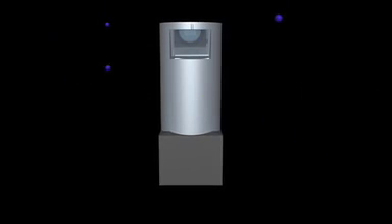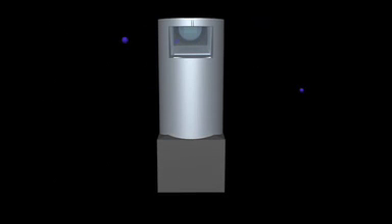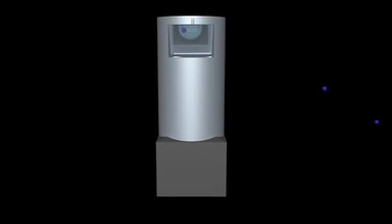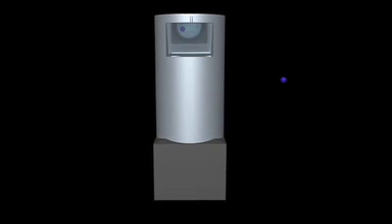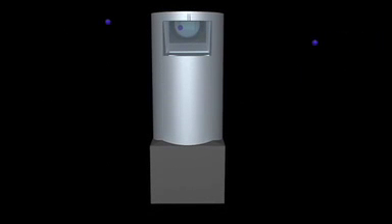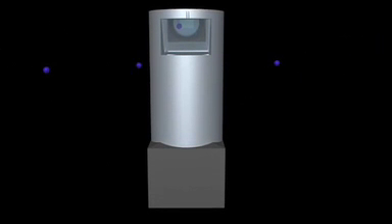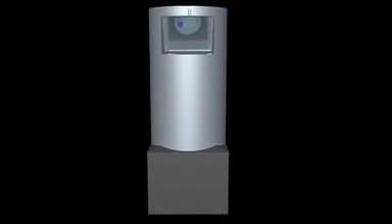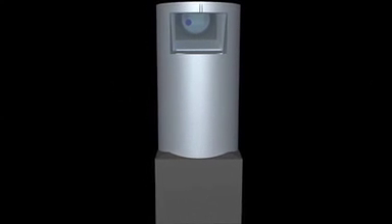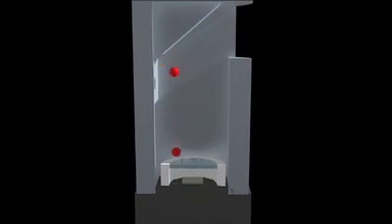As seen here with a periscope type of camera, using a stainless steel housing, mirrors, and lead protection, the effects of gamma radiation are reduced. However, there is virtually no protection from neutron radiation as there is a direct open path to the camera's electronic components.